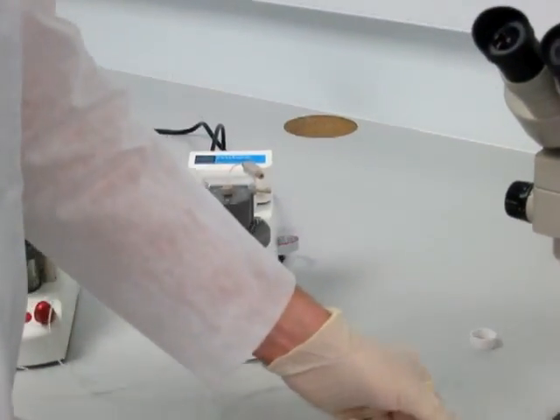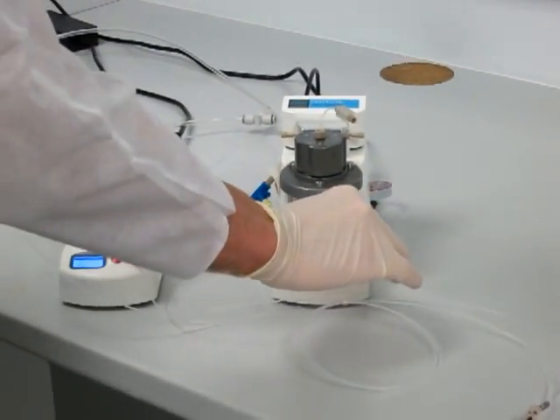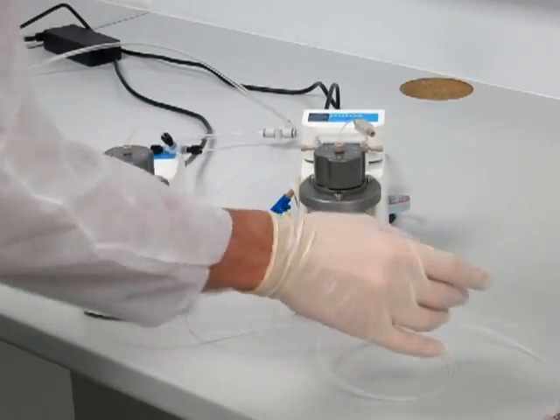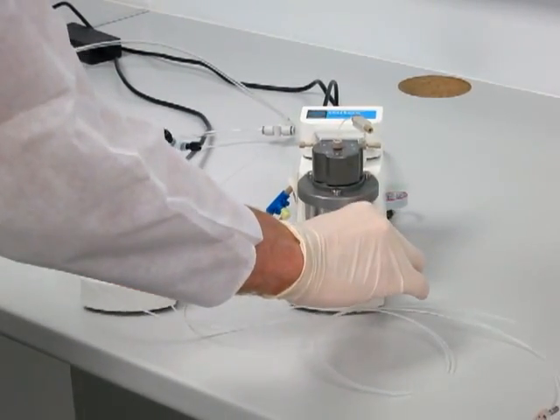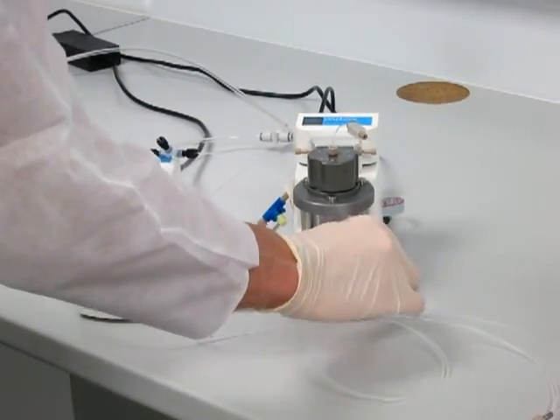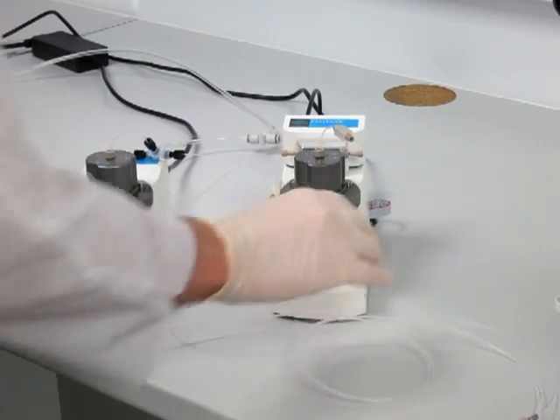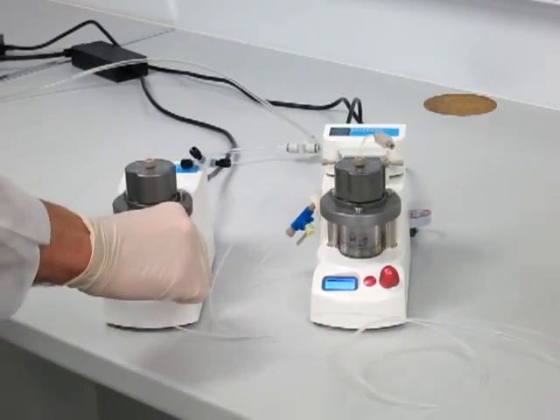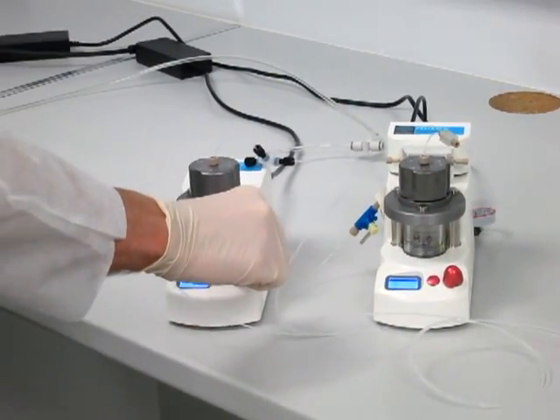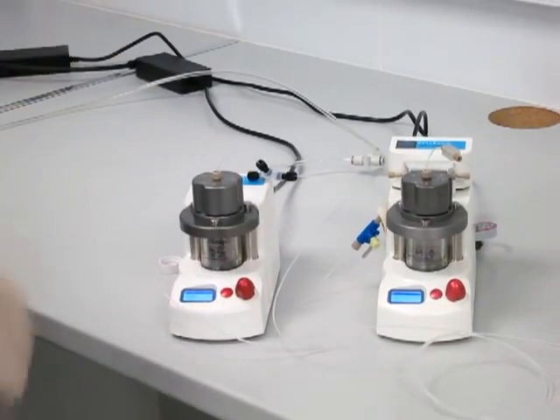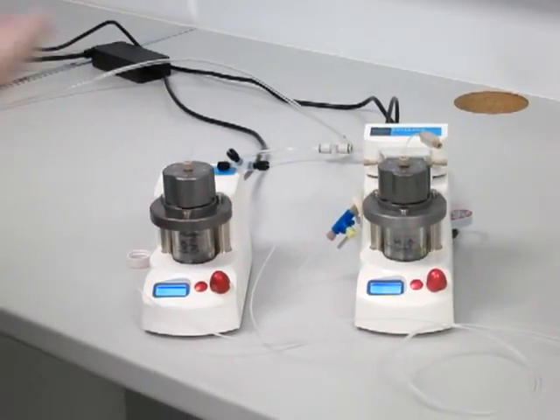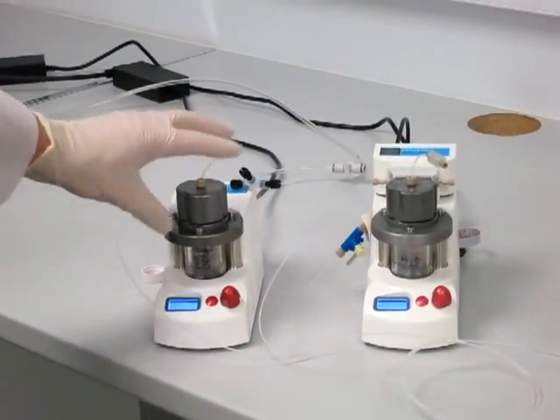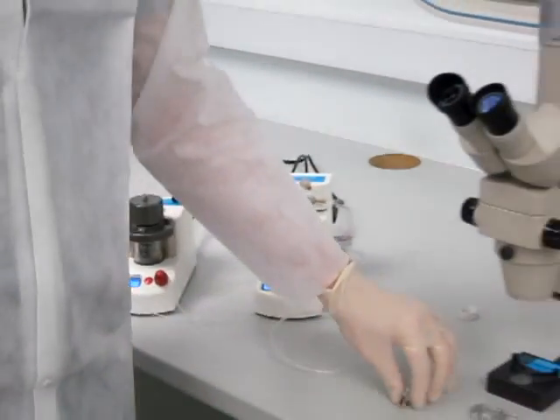So what we're going to do first is we're going to prime these lines. So we're going to set some. So from the P-pump, I can scroll through, and I'm going to set a pressure. That clicking noise is the pump basically setting the pressure in the reservoirs.